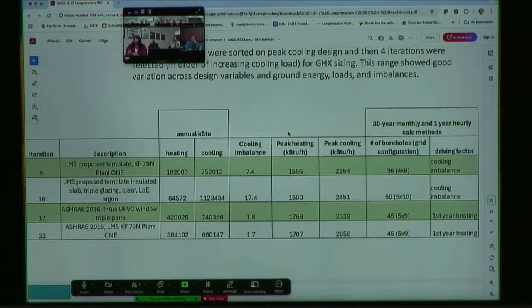Basically, iteration 5 is more or less the best combination, and it resulted in the lowest number of boreholes. So that's a good thing. That means we're saving quite a bit of money by going through this process and finding the right configuration that can reduce the size of the ground heat exchanger. So just looking at this top line, you'll see we have about a cooling imbalance of 7.4, meaning there's about 7 times more cooling energy rejected to the ground than is sourced. And the driving factor for sizing the borehole was that cooling imbalance.